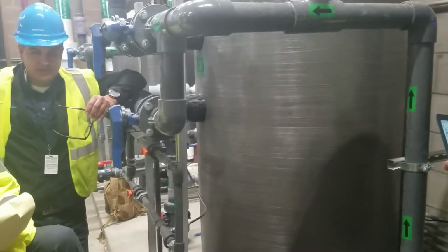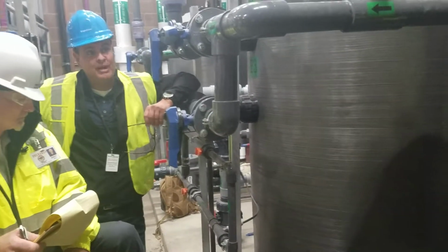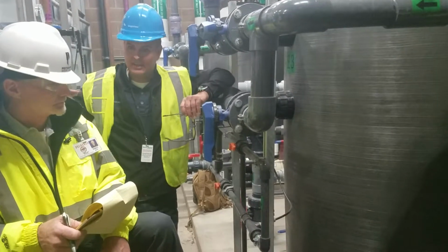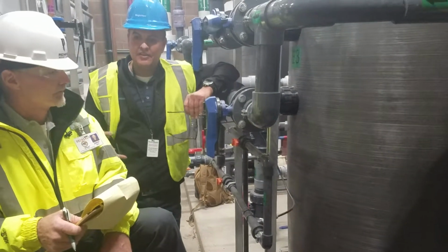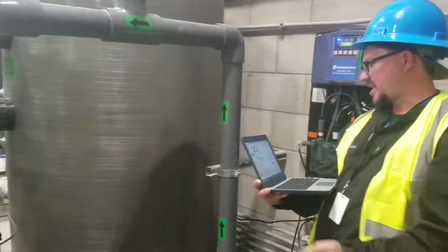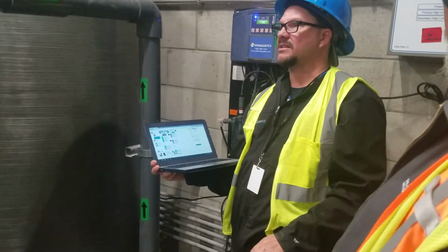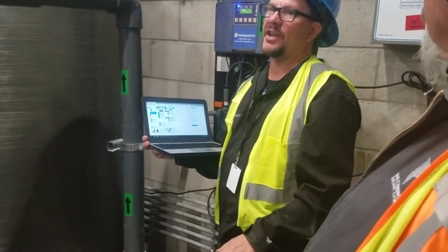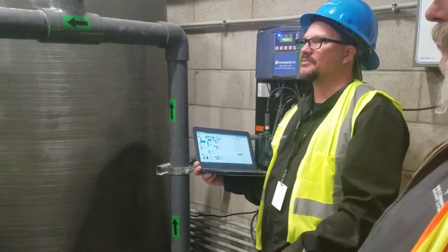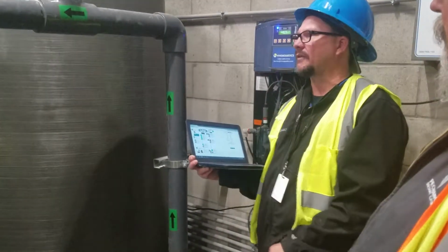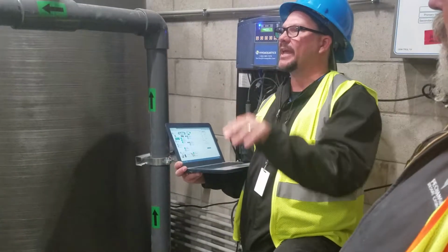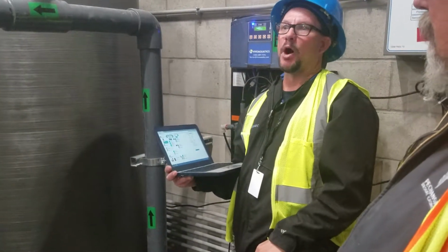We have equipment rooms where we're tying in kilowatt hours, pump amp draws, flow meters, everything tied into the controller, and then on your dashboard, you would be able to see all that information. You've got relays on this controller not being used right now that we can go ahead and set you up on secondary type feed pumps and things. If you want to, ancillary dosing, enzymes, all those things at night. You do not put clarifiers and enzymes during normal hours. You want all that obviously going in at night, post backwash.